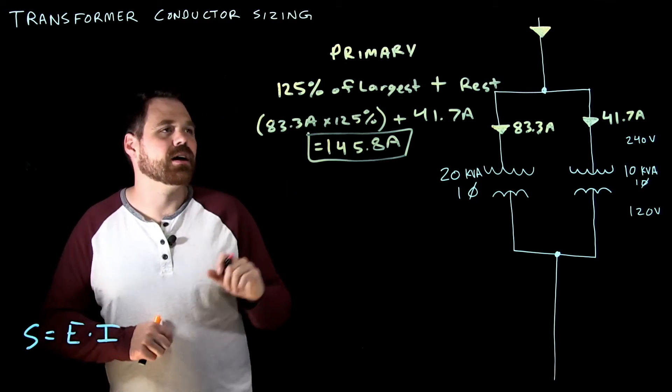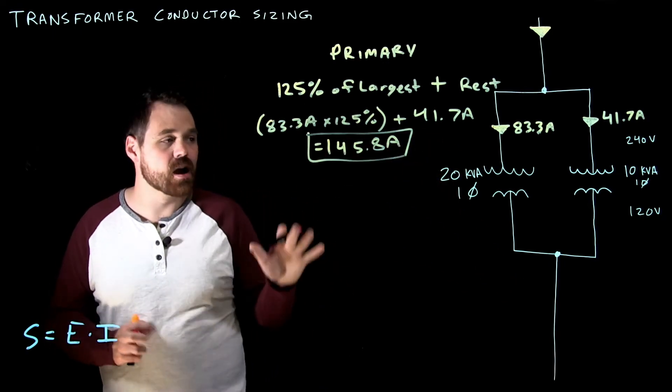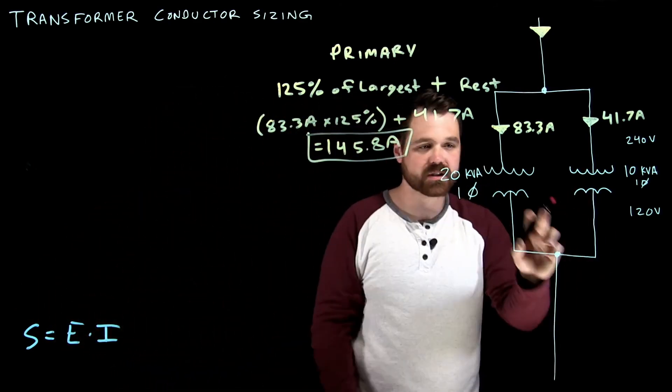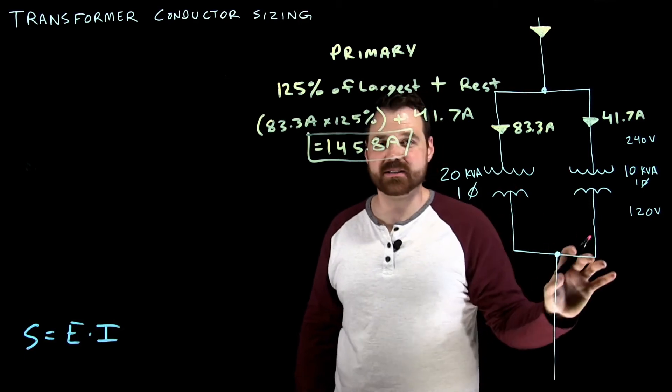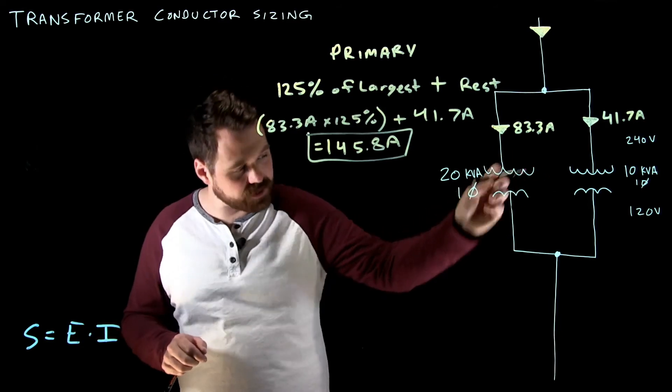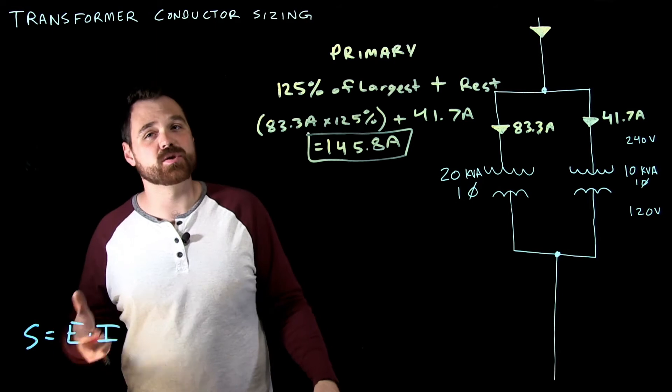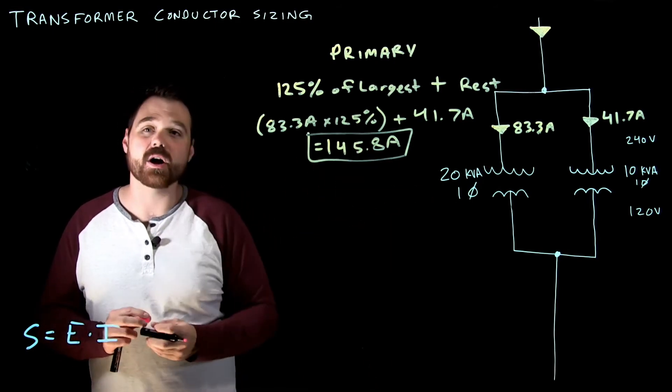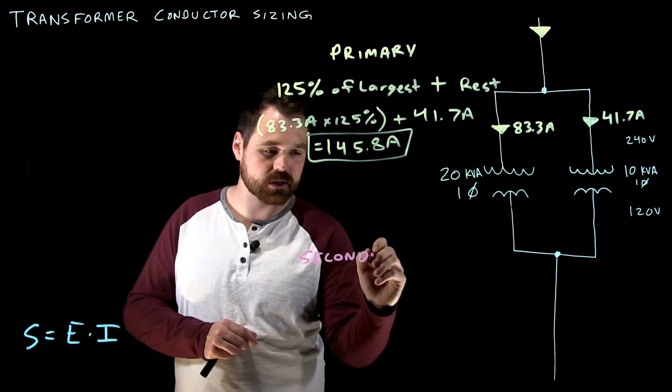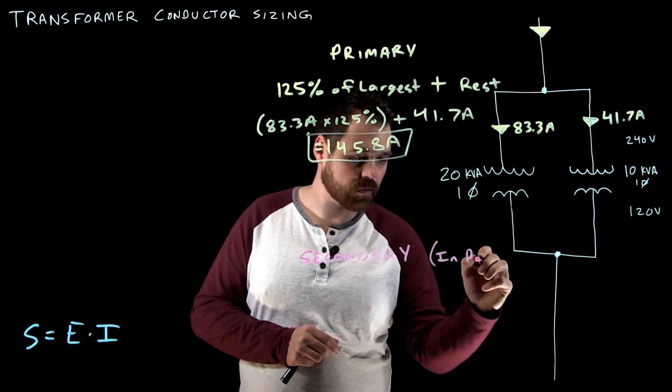All right. Now I want to talk about the secondary of the transformer. So that's the primary. The secondary is easy. The thing here we have to remember is this only matters if the secondaries are in parallel like this. So because these secondaries are connected together, we need to apply the rule. If they weren't, if they were not connected in parallel, and they just went out to feed separate loads, you would treat the secondaries as individual transformer conductors. But because they are parallel, so secondaries, secondaries, and I'm just going to put in parallel.